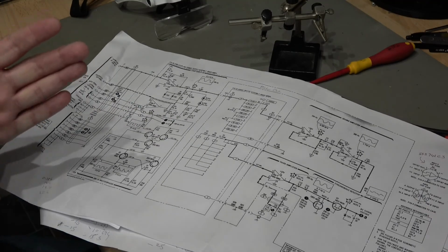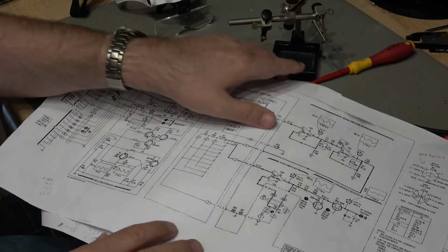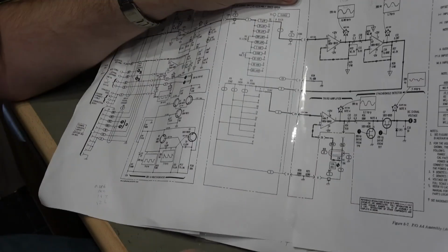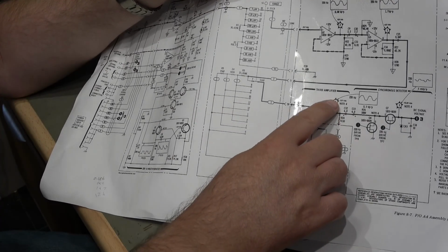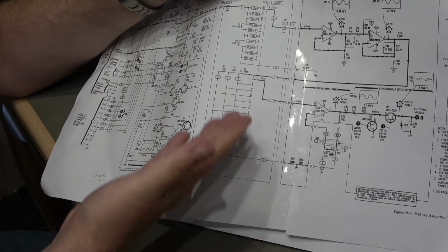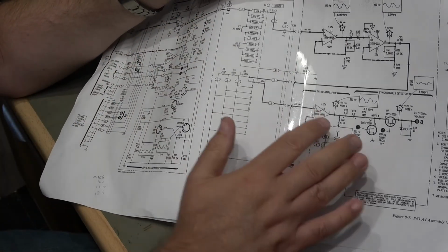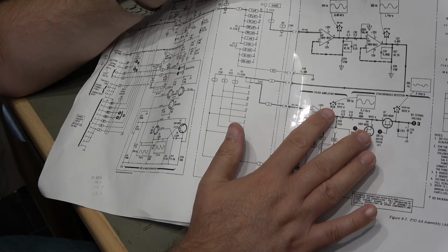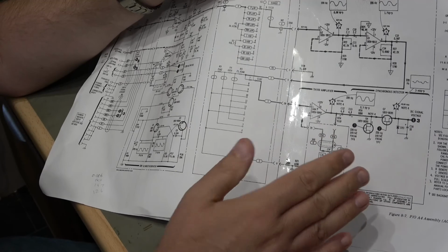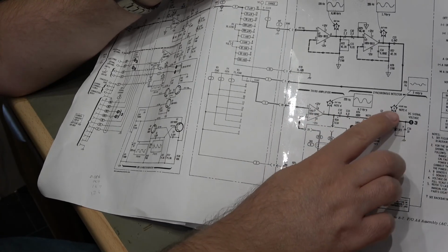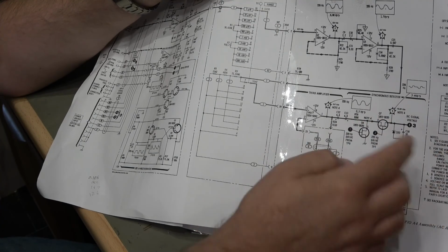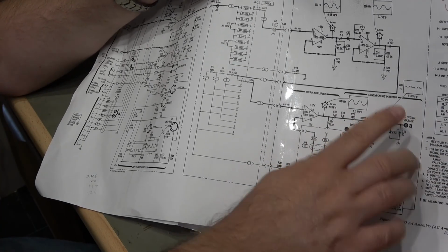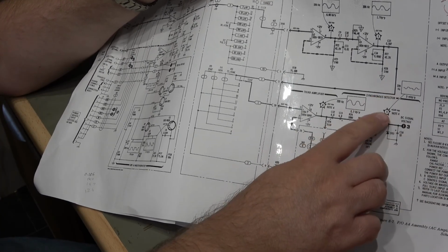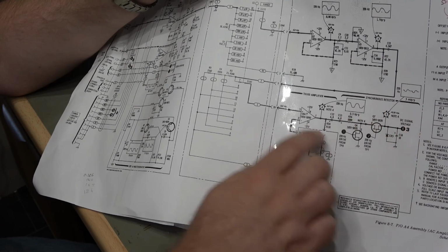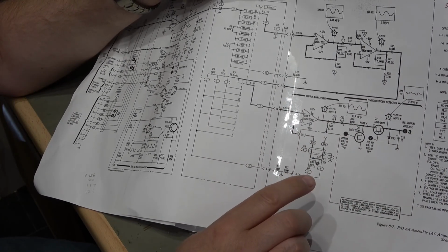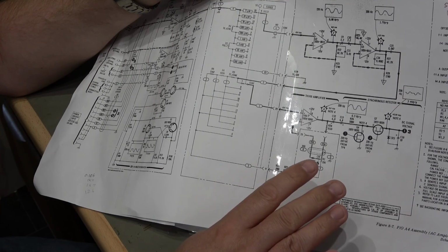And what I've done next then is I've applied a full signal and I've measured it just here, 0.4, which is basically the output of the first couple of attenuators. Now, for each range, as long as I put a full range signal in, each range should read the same, and it does. When I come over here, I should read round about 0.2 volts. Again, on every single range, they should all be identical. Now, I'm actually not reading that. So to cut a long story short, the voltage must be varying somewhere.